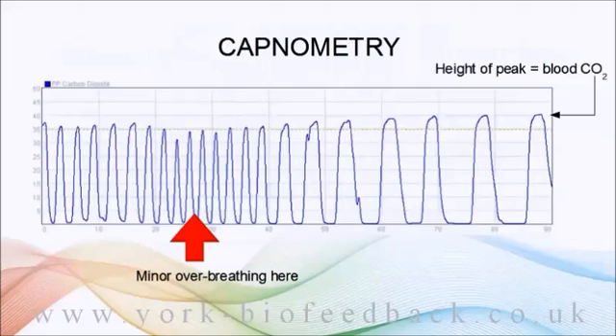You get a sequence of peaks — one for each breath. Carbon dioxide clearly peaks during exhalation, at the end of the exhalation, then drops to zero when you're breathing in. The distance between peaks gives you the breathing rate on a breath-by-breath basis.